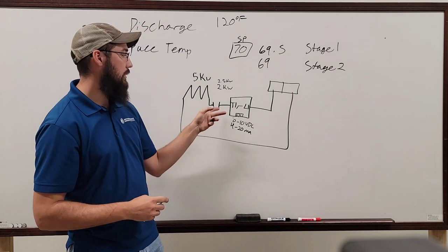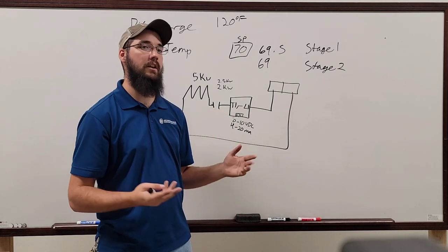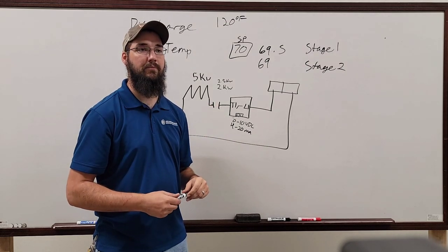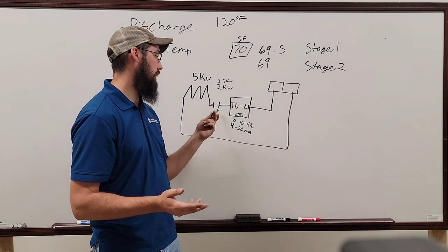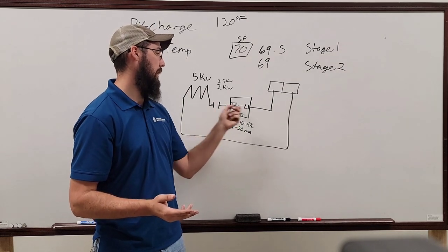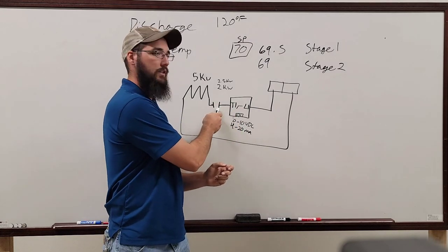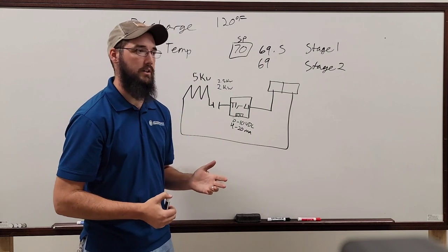And so if your fan proving switch is open, you've got a high limit open, anything of that nature, this contactor will not draw in. Just keep that in mind. And don't let this confuse you and think, oh, well, how do I have both? How can it be both? No, it's not both. This is a safety device. That's all it's being used for at that point.